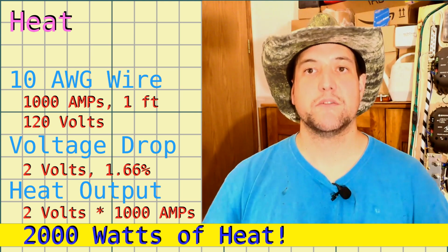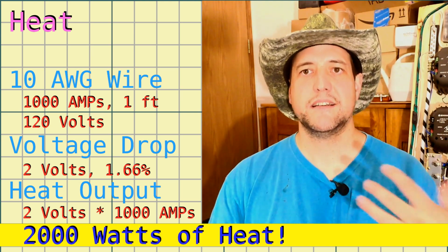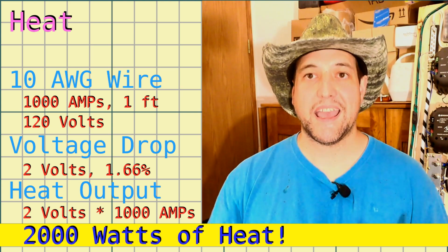And that's important. The resistance of the wire directly determines how much heat is released over a given area, and that is very, very important. So when we're engineering these things, I calculate the heat loss because I don't like my conductors getting hot. In fact, I don't like them to rise at all. I over-engineer big time. I like things to work at the maximum worst case condition with very little problems. I don't like conductors heating up. I don't like much things changing. So when you see my stuff built and you go, oh my gosh, Reed, that's so overbuilt, yes, it is, for a reason. I like my conductors cool and calm. Cool like cucumbers.